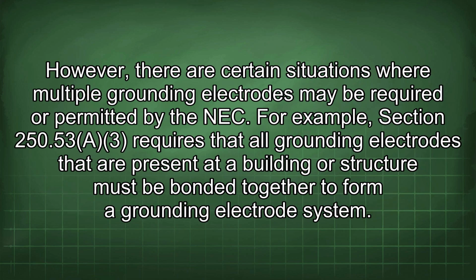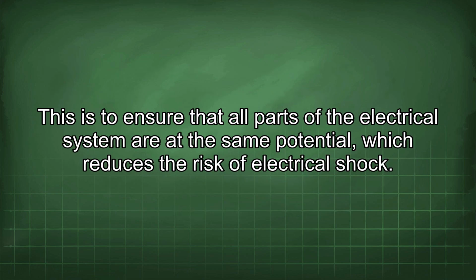However, there are certain situations where multiple grounding electrodes may be required or permitted by the NEC. For example, Section 250.53(A)(3) requires that all grounding electrodes that are present at a building or structure must be bonded together to form a grounding electrode system. This is to ensure that all parts of the electrical system are at the same potential, which reduces the risk of electrical shock.